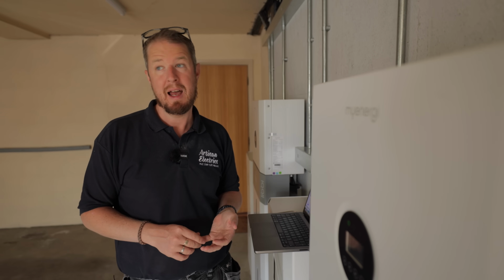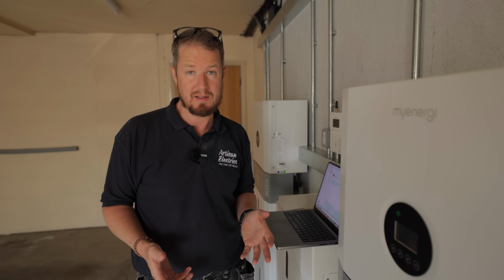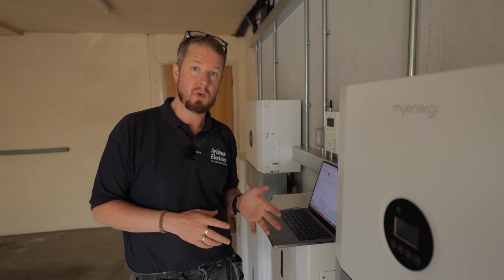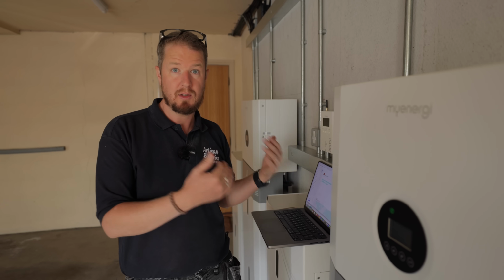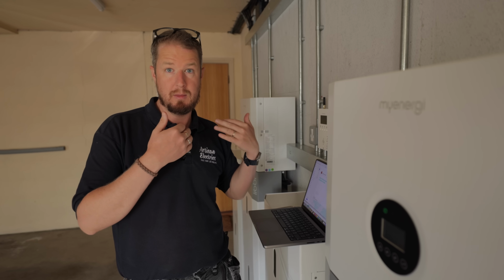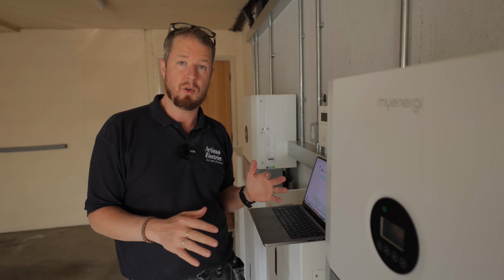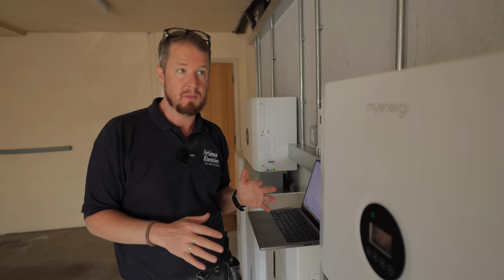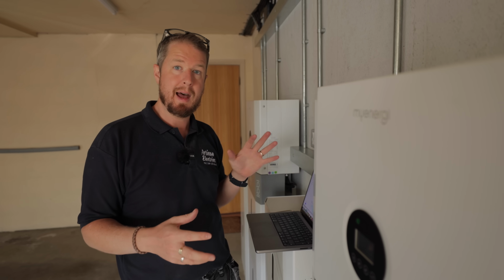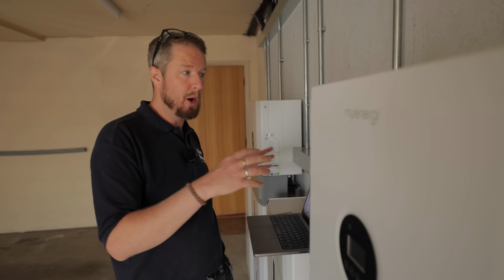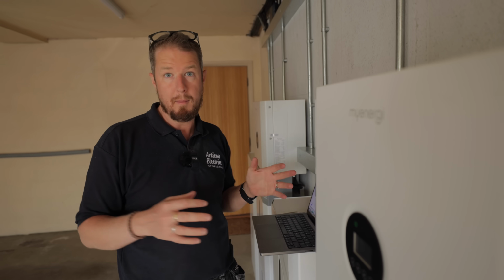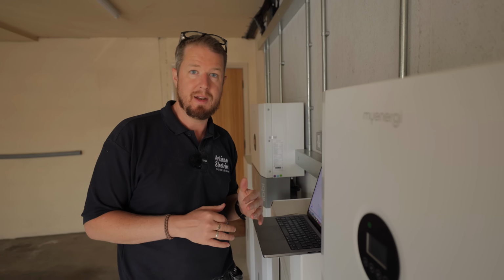They can take ages, and sometimes they can require you to spend a lot of money to upgrade the local transformer and things before they'll let you connect a system. Or they might impose what's called an export limit, where you set in the software a limit on the maximum discharge that can happen to the grid at any one time from the systems. But either way, it means that we have to make sure that the system can monitor everything that's going on, monitor the export and ramp it down if necessary.